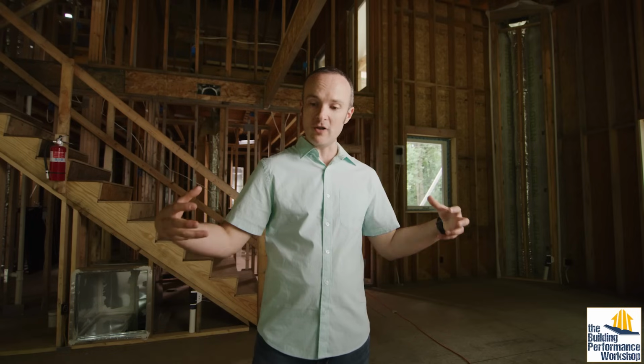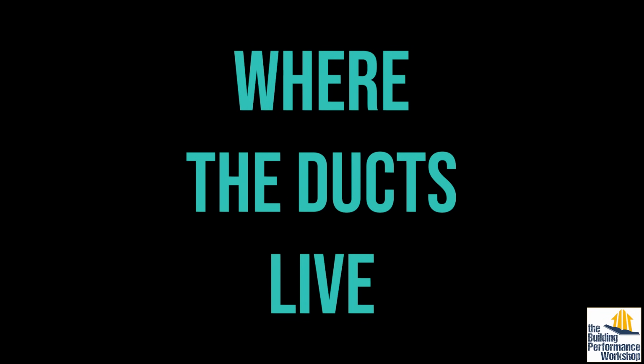This way, what we're doing is supplying to all the bedrooms so that all of the air flows in a specific direction, and we know how that works. All of the air is going to be returned from the entire house into this room, where it then is returned to the equipment for more conditioning. That's kind of a beautiful thing. So this central return has a 90-degree turn or two that it's taking before it gets to the equipment, and that's important because we don't want to hear the heat pump every time it turns on or turns off in the crawl space below us.